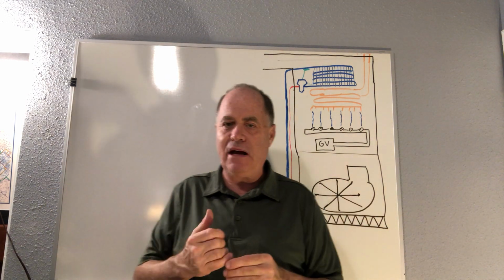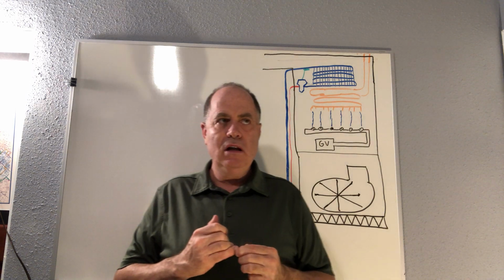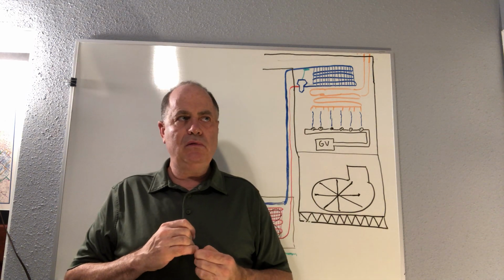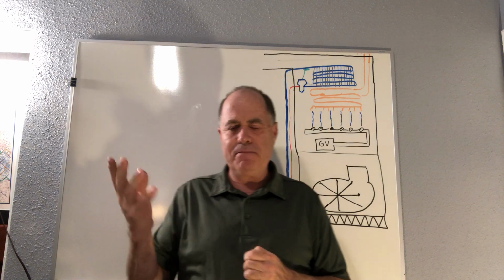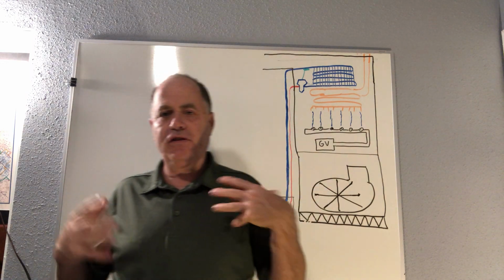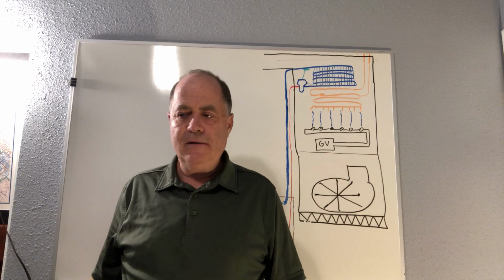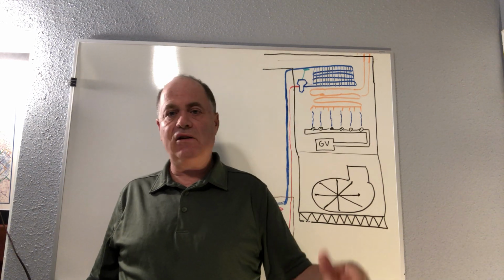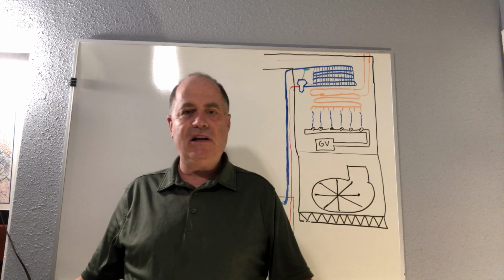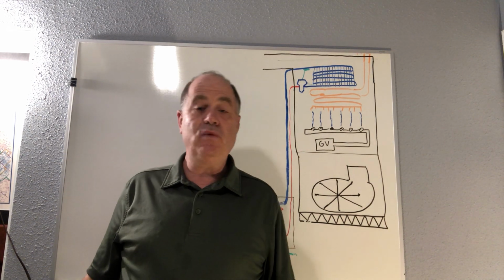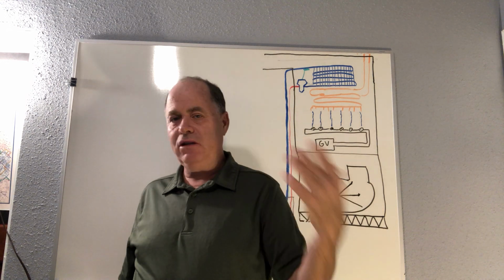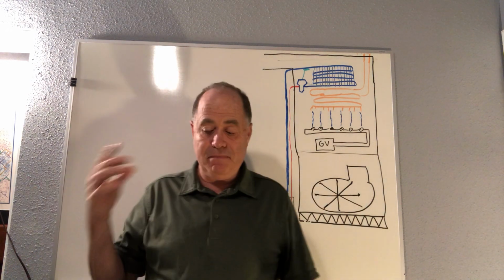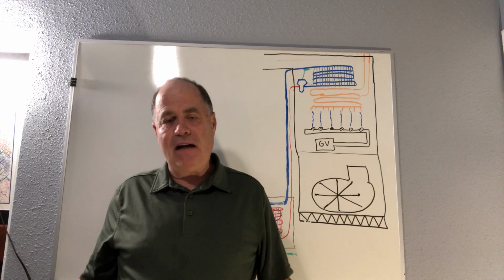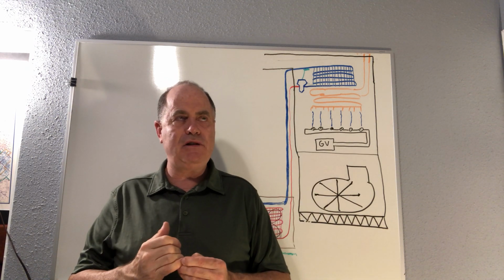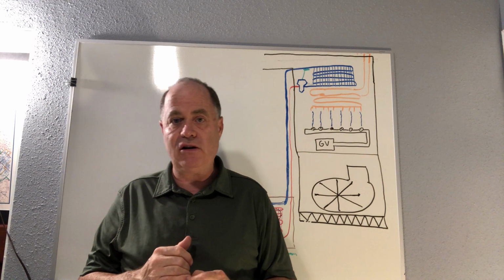Now the one exception for that, which may sound a little unusual, would be dryers. They don't require that for dryers, and the logic behind it is that it's not the kind of thing that starts automatically in the middle of the night. No dryer is just going to say, all right, you put wet clothes in here 3 hours ago, I'm going to start at 2 a.m. We don't have that. They're manually started. So the thought is that because of that, it's not required. The code treats it like a portable piece of equipment: washers, dryers, ranges, stoves, this kind of thing. Okay.